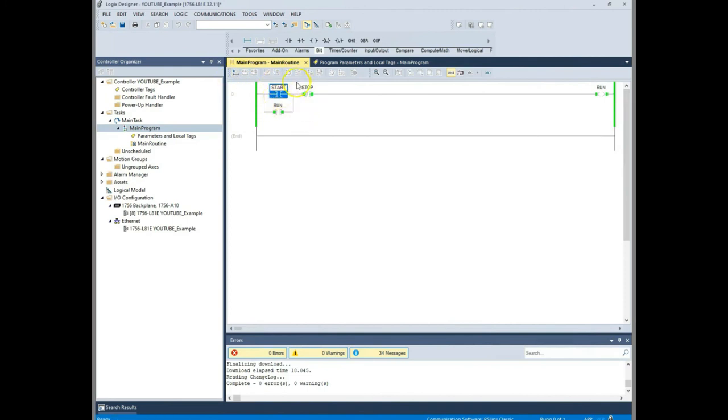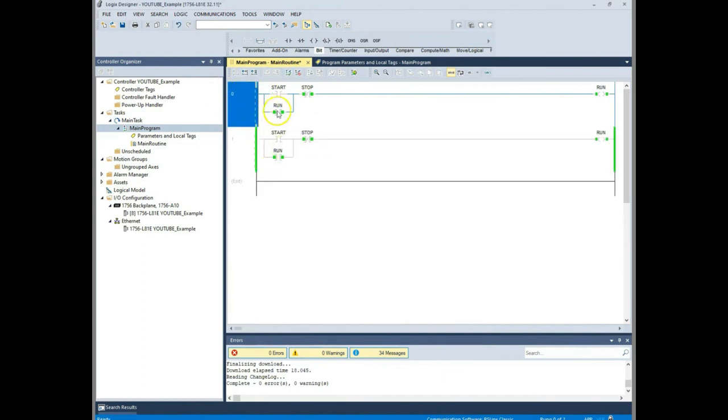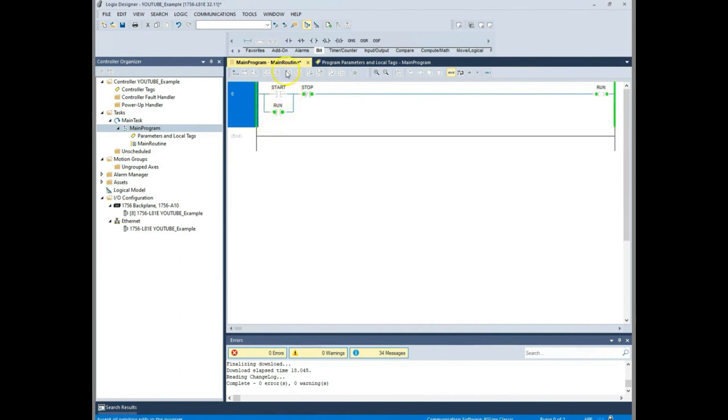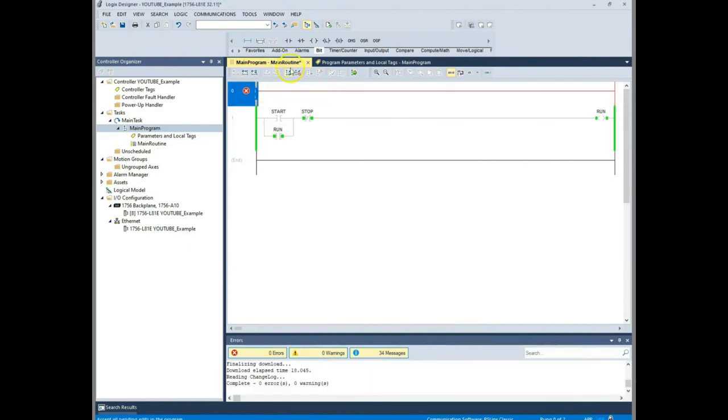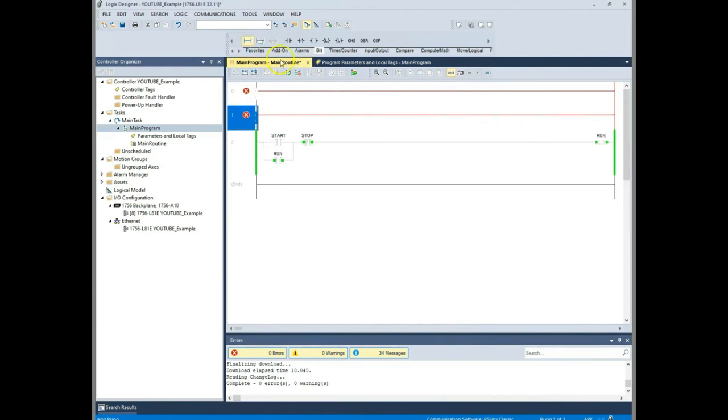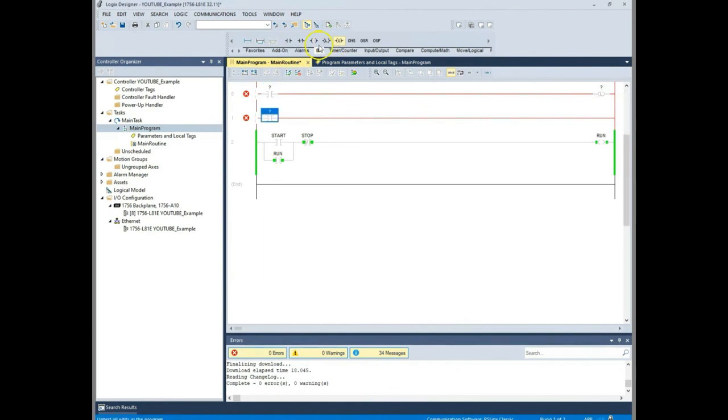What we're going to do is we're going to use these same tags, but we're going to use a latch and unlatch. Now what latch and unlatch does is it's different than our OTE. Whenever we enable a latch, it's going to stay high until we enable an unlatch. And so it's another way to do a seal-in circuit. Now I'm online. Normally you would go offline here, but what I'm going to do is I'm going to double click and you can see here that what it does is gives us a redundant rung and I can make changes online. So I'm going to delete this first rung. I'm going to add in a new rung. And then I'm going to actually add two rungs and I'm going to use two XICs. Then I'm going to use a latch and then I'm going to use an unlatch here.